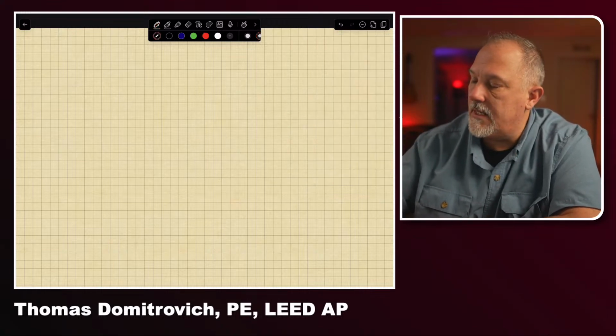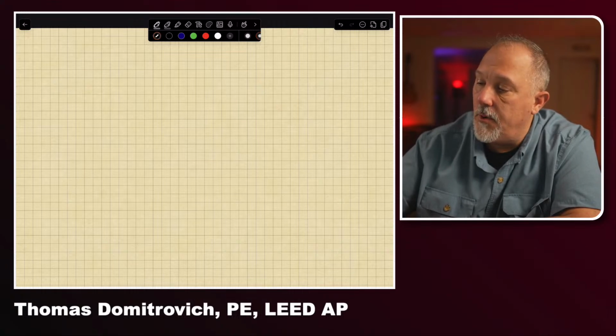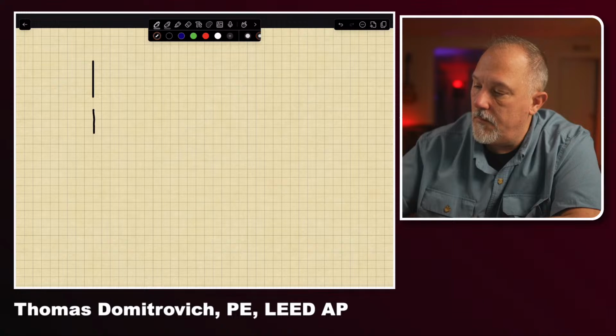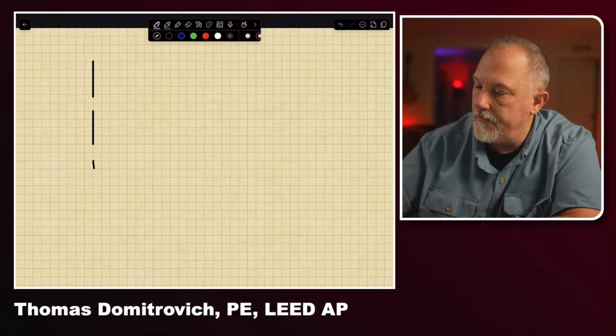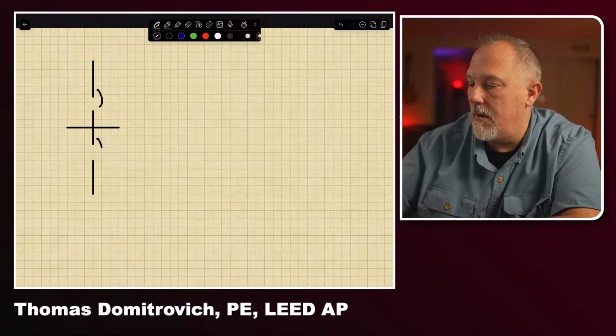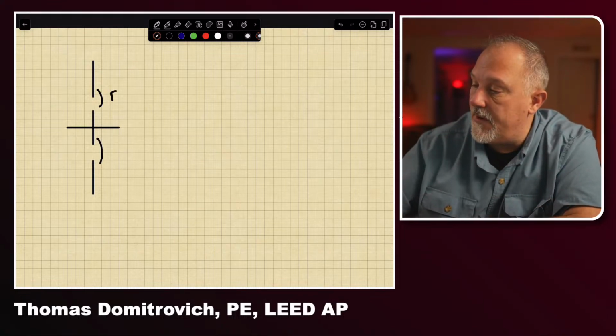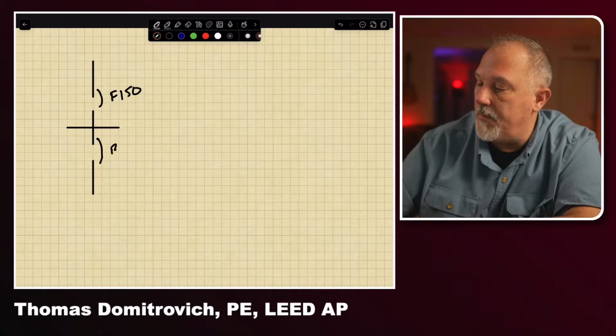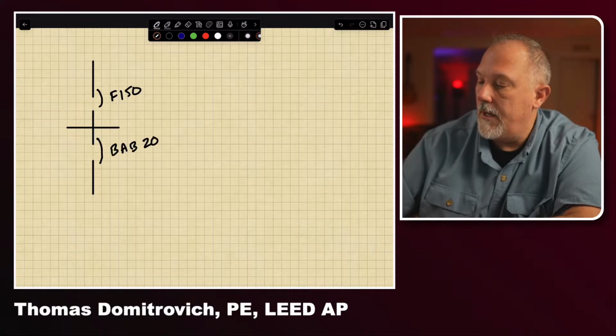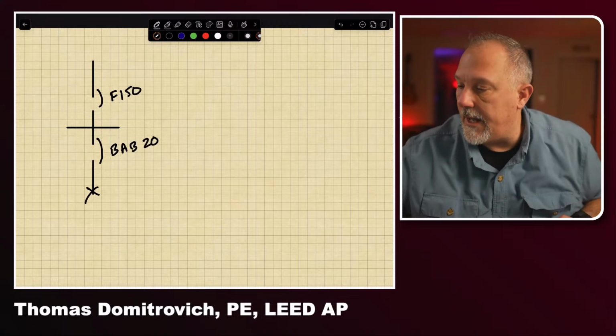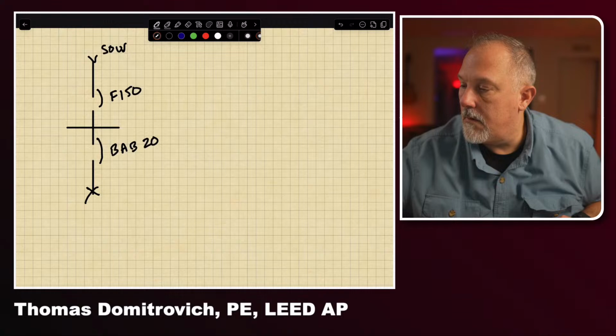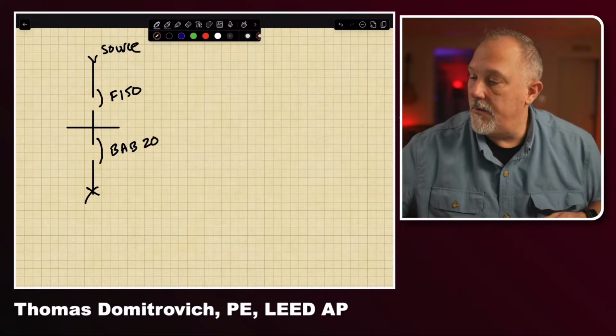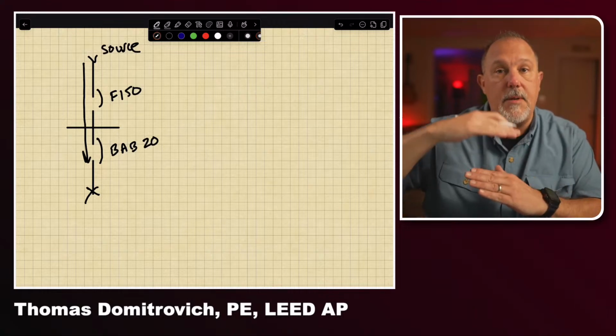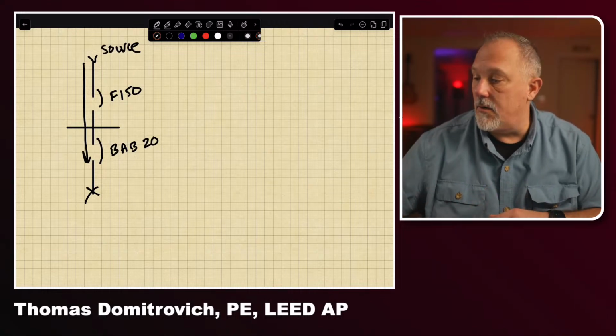what we do for those tables is we basically take two breakers. We put them in a lab. And in this case here, I would have the F150 upstream of the BAB20. And we basically have a source.